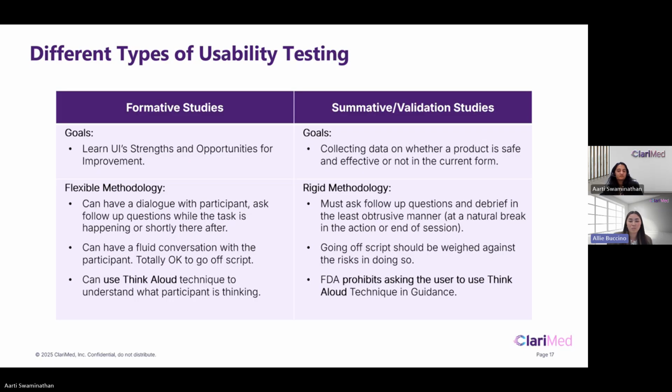Should they use a swab and a pipette? Should they use a dropper tube? There are so many different materials you can use for those steps, and a lot of them are a lot more user-friendly and less risky than others as far as use errors. So you can test out different materials and workflows in formative studies and help guide your design, as well as just testing the design that you think might be the best. It's helpful to hear from users throughout, and then you can really design it for them.